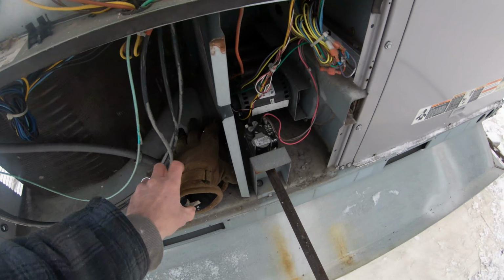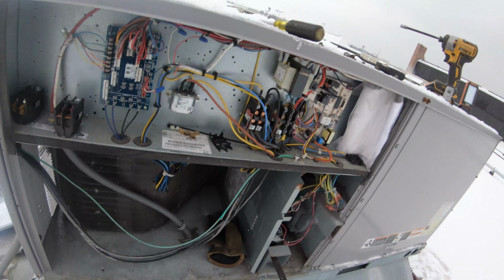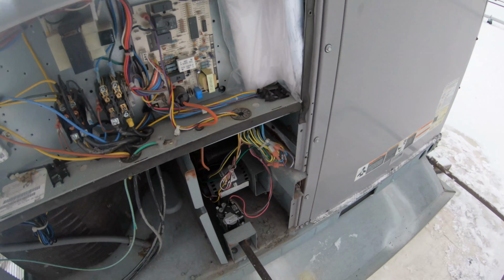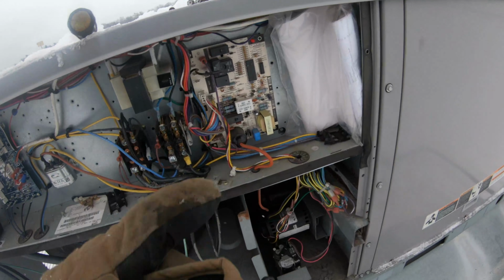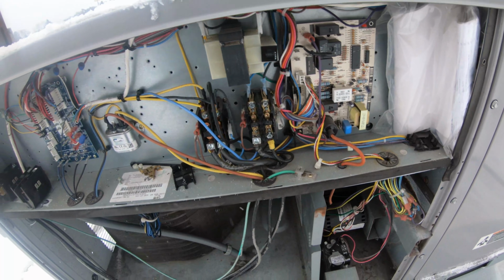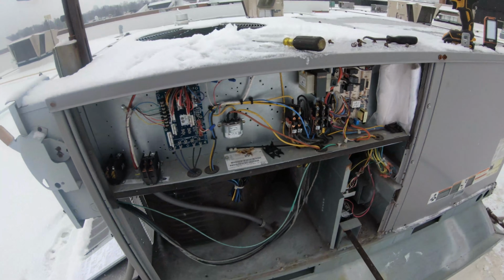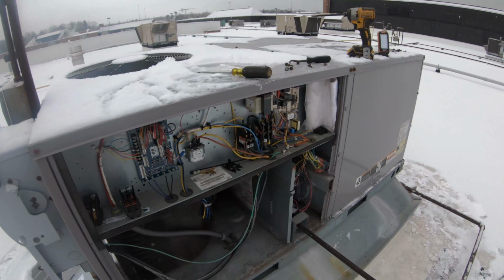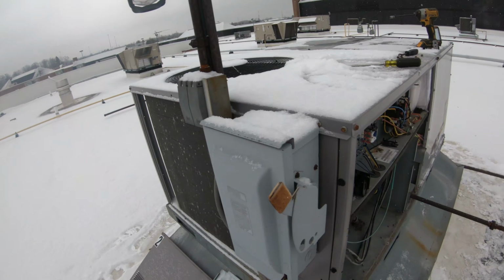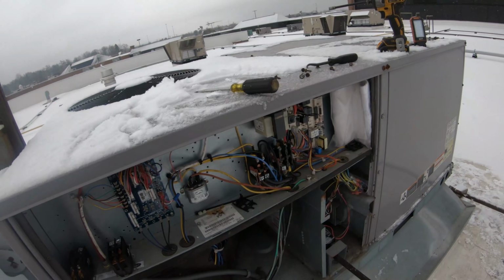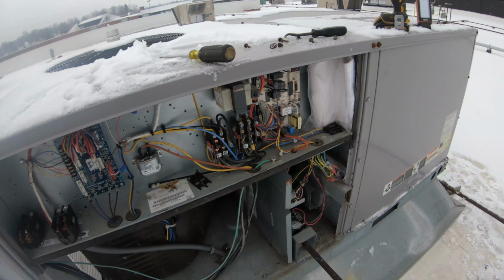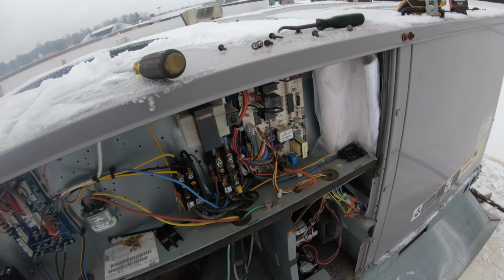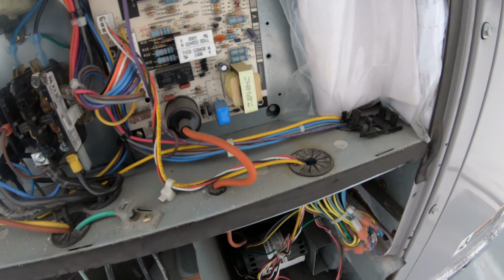All right, well, we got her fired back up. I'm gonna let it run for a little while, probably cycle it on and off a few times, see if I can get this board to give me those codes again. It was on a lockout and, oh man, my memory - internal control fault. So at the very minimum, we're probably gonna be writing up 2 contactors and an ignition control board, plus a flame sensor and igniter, just for good measure.